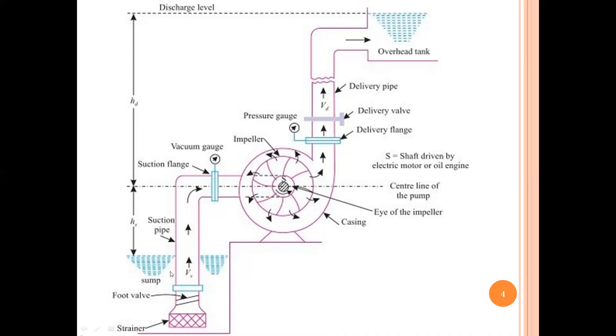Important terms in centrifugal pump: suction head is the vertical height from the center of your pump — the eye of the impeller — to the water surface in the below tank. This is my delivery pipe, and the distance from the center line of the pump to the water level in the overhead tank is called your delivery head. Both are vertical distances. You also have a suction flange and delivery flange to connect pipes, but the important parts are impeller, casing, delivery pipe, and suction pipe.